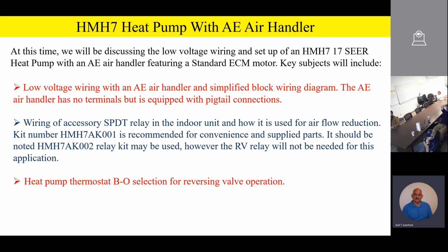So basically what this is, it's going to be a little relay mounted on a board, and it's going to have some pre-made harnessing or pre-made wires that you can just hook up. And then it's also going to have a bi-flow filter dryer in that kit. And so this unit does not come with a factory installed filter dryer brazed into the outdoor unit. It's something that the contractor, you guys, will have to add when you install these things. And again, we're going to recommend that 001 kit for convenience and all the supplied parts.